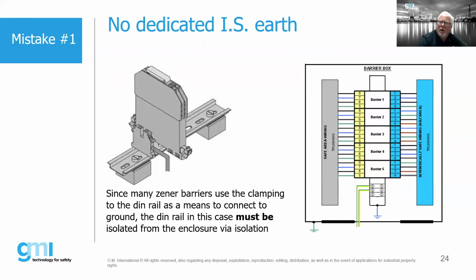On our right-hand side, we'll see intrinsically safe going out this way, and we have our safe area wiring coming out this way. We notice that we have dedicated earthing, and we have our IS earth, and that's separate from our normal dirty earth. That's typically one of the biggest issues that we find. And quite frankly, this is also a reason why a lot of people don't like using Zener diode barriers, because generally speaking, when we use them, we have to ensure that we have a good clean earth.